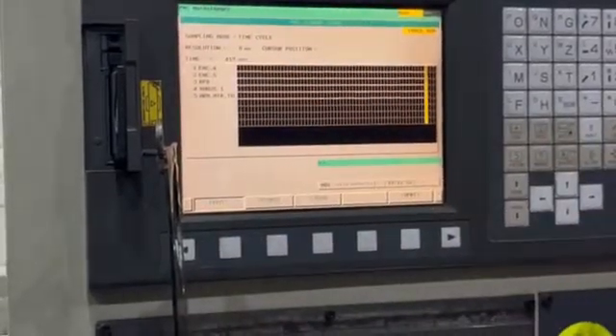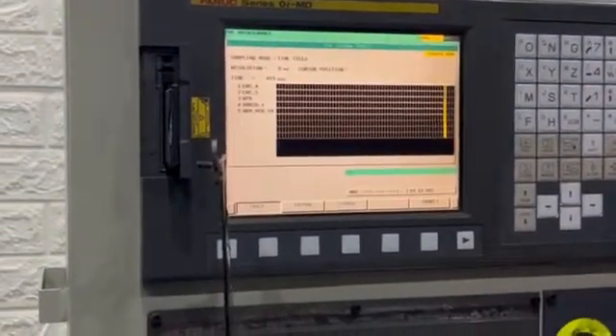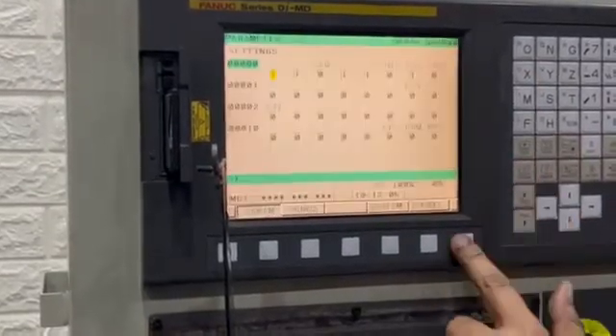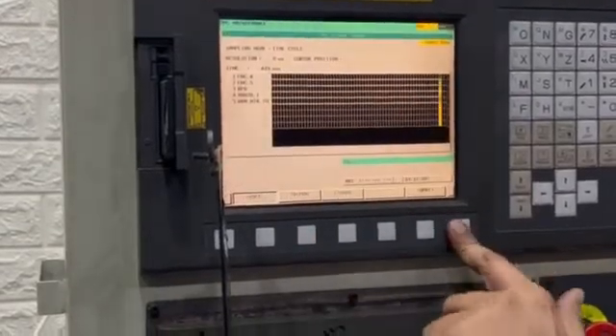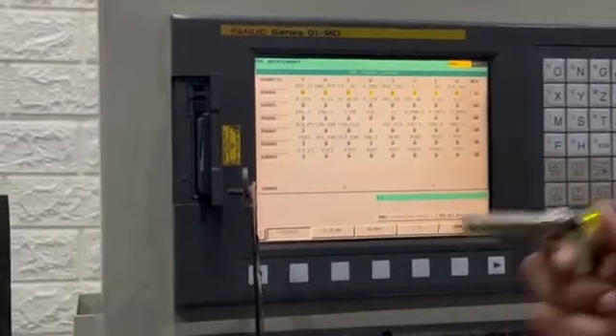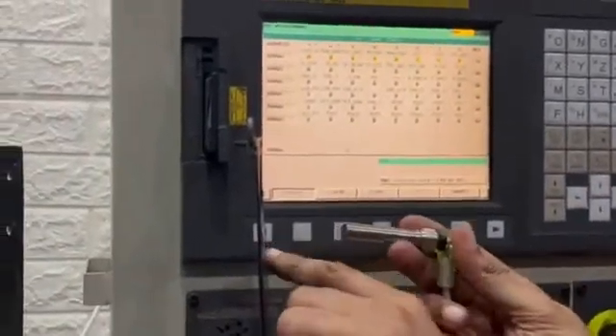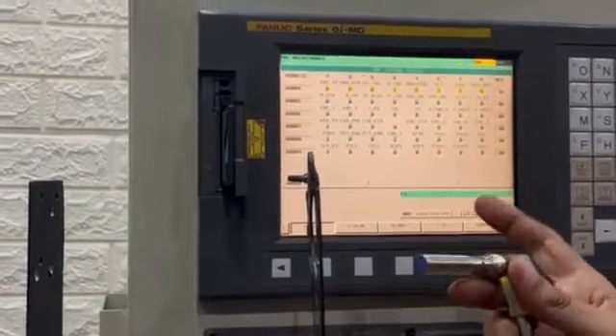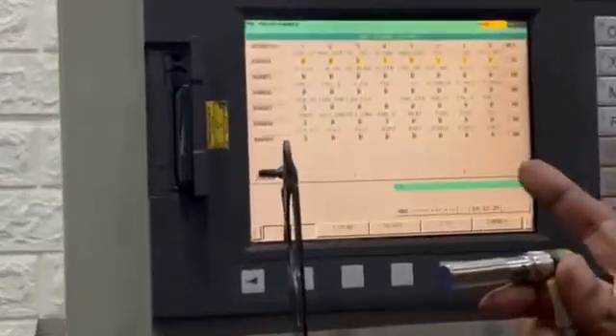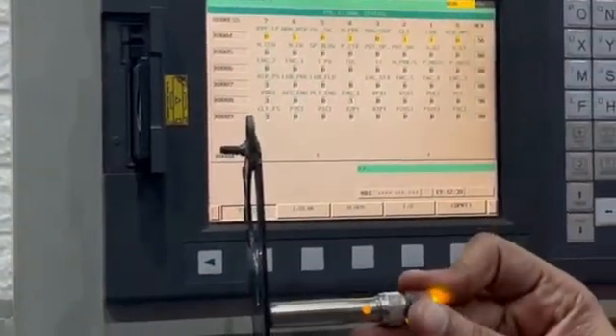I will make the signal low just for a fraction of a second. That dip in the signal cannot be seen or recorded with the eyes, but it will get recorded in the oscilloscope. This is the signal X4.6. When I move this proximity sensor in front of the hole, the signal will dip for a fraction of a second. It cannot be seen with our eye, but the oscilloscope or the trace function will detect the same.